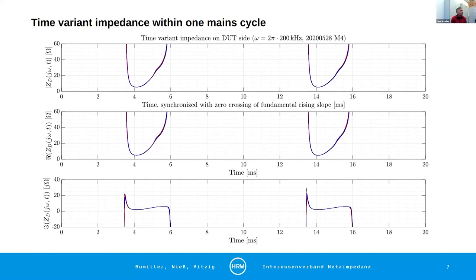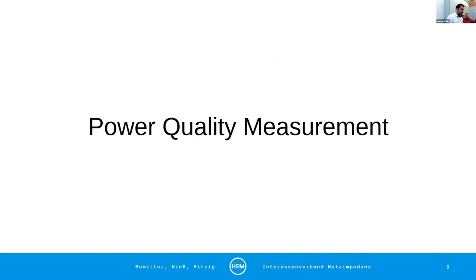You are seeing this device is coming from a capacitive impedance going to low inductive impedance and going back over the capacitive impedance to high impedance. It's going down even in this small component to a few ohms, about five ohms for a very short time. And you see these measurements are several measurements over time. This process is very constant over the line cycle. If you synchronize it with the line cycle, one measurement lies over another. That is one to show our possibility. Then I change to a second technology of ours, which will be presented by Jan.